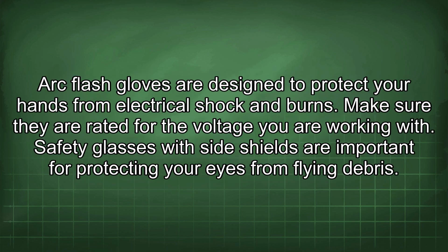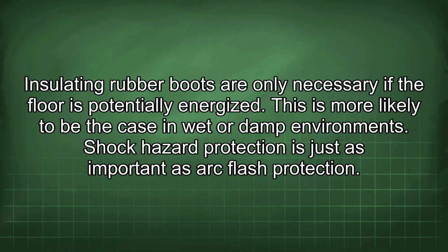Arc flash gloves are designed to protect your hands from electrical shock and burns. Make sure they are rated for the voltage you are working with. Safety glasses with side shields are important for protecting your eyes from flying debris. Insulating rubber boots are only necessary if the floor is potentially energized. This is more likely to be the case in wet or damp environments.